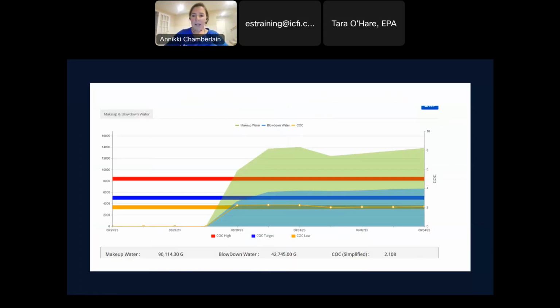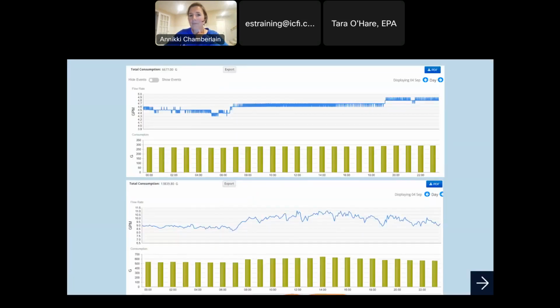Here's one more. Again, a really low cycles. Basically, this is the blowdown right here. What did we see in that last one? It should be coming on, coming off, coming on, coming off. Boom, I know right now, without even going to the site, that my blowdown is stuck open. Call the service provider, let them know, and they can go from there. This bottom one is the makeup, and again, this should be responding every time there's a blowdown, but everything's just pretty much wide open.